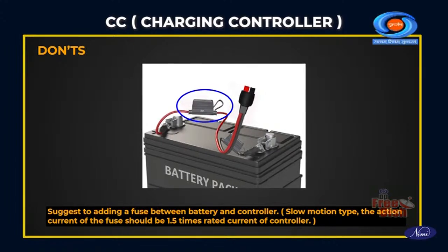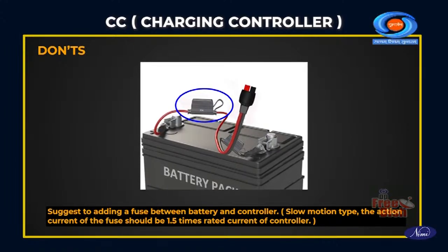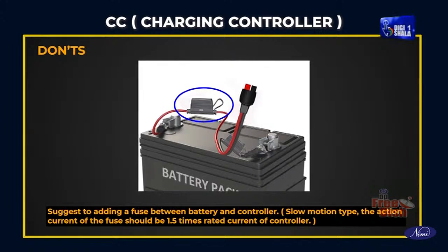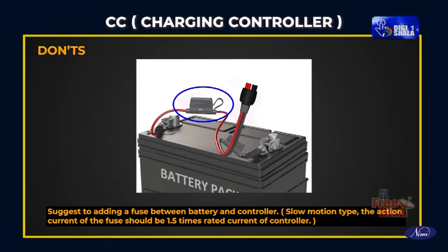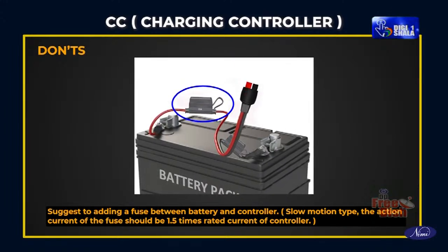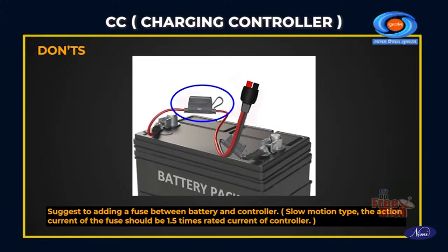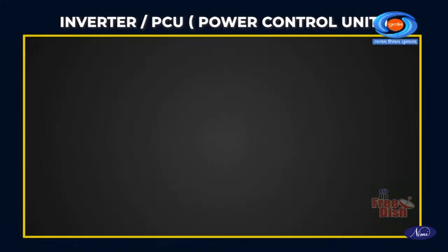Suggest adding a fuse between the battery and controller. Slow motion type: the action current of the fuse should be 1.5 times the rated current of the controller. Inverter or PCU, power control unit.